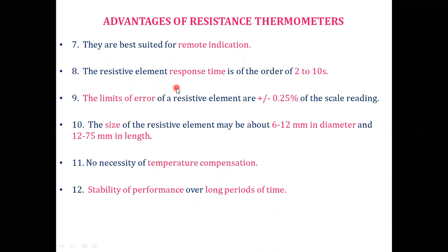The resistive element response time is of the order of 2 to 10 seconds. It is going to give some output within 10 seconds. The limit of error of a resistive element is plus or minus 0.25 percentage of the scale reading.